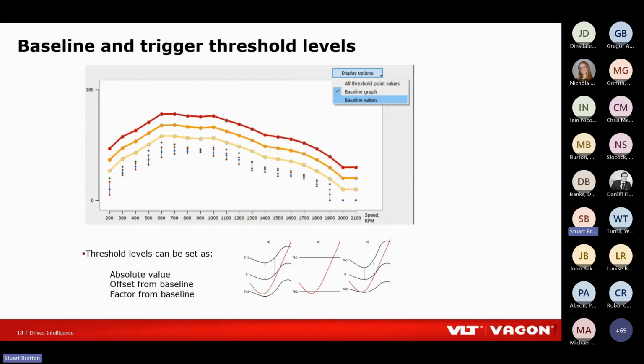So just to give you an idea of what it might look like in our drive programming software, the dots you see on this graph are like the mean, peak and minimum values that it recorded. Let's say this is vibration, and then the yellow, orange, and red lines are the thresholds and the alarm levels that maybe the drive has automatically generated based on the data it captured when it ran the baseline level. And you can set either absolute values for the thresholds, or you can offset the thresholds from the baseline, or you can make it a factor, so 1.2 times the levels that were captured during the baseline. Completely up to you. Like I said, most people probably just let the drive set the baselines, but other people with a lot of experience of vibration monitoring, for example, may have other ideas on how they want to set up the thresholds.